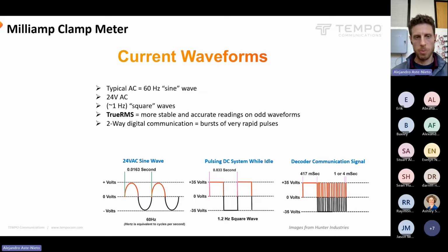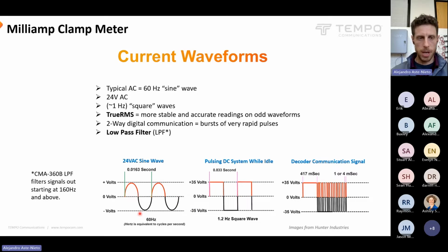When there's two-way digital communication, there are very rapid bursts happening on the two-wire path. As you can see here in this image, there might be the slow pulsing happening, but then all of a sudden there are very rapid bursts adding to the amount of current going on. But we can help ignore some of those bursts messing with our readings by engaging a low pass filter. The low pass filter of the CMA 360B starts to ignore anything above 160 hertz, and the higher the frequency, the more it'll ignore it. So that's helpful to know on those kinds of systems.